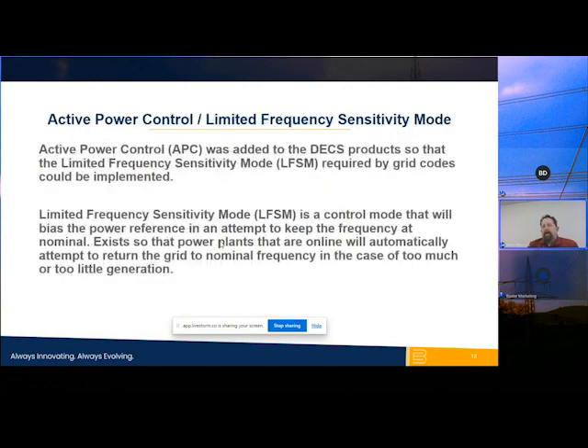Now, the last component that the voltage regulator is doing is the active power control, and what we call the limited frequency sensitivity mode. The active power control was added to the DECS so that the limited frequency sensitivity mode required by grid codes could be implemented. Limited frequency sensitivity mode is a control mode that will bias the power reference and attempt to keep the frequency at nominal. The purpose of it is to keep power plants online and to automatically return the grid to nominal frequency if it were to vary.